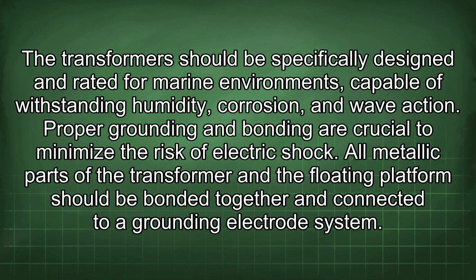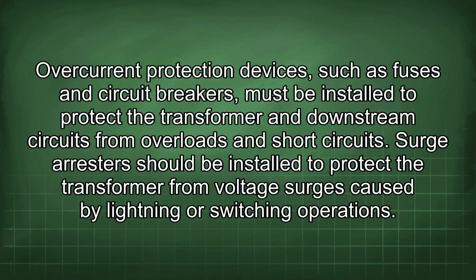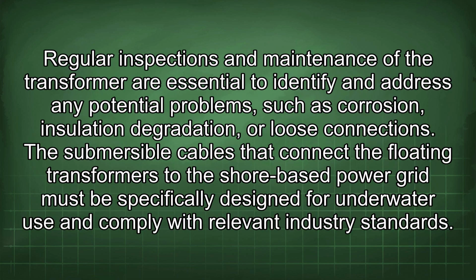The transformer should be specifically designed and rated for marine environments, capable of withstanding humidity, corrosion, and wave action. Proper grounding and bonding are crucial to minimize the risk of electric shock. All metallic parts of the transformer and the floating platform should be bonded together and connected to a grounding electrode system. Overcurrent protection devices, such as fuses and circuit breakers, must be installed to protect the transformer and downstream circuits from overloads and short circuits. Surge arresters should be installed to protect the transformer from voltage surges caused by lightning or switching operations.